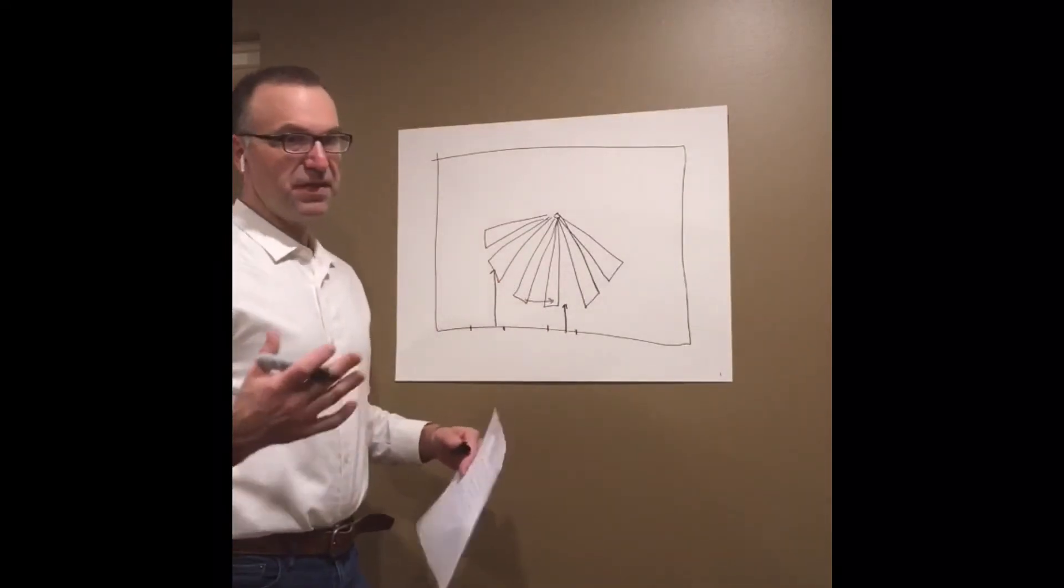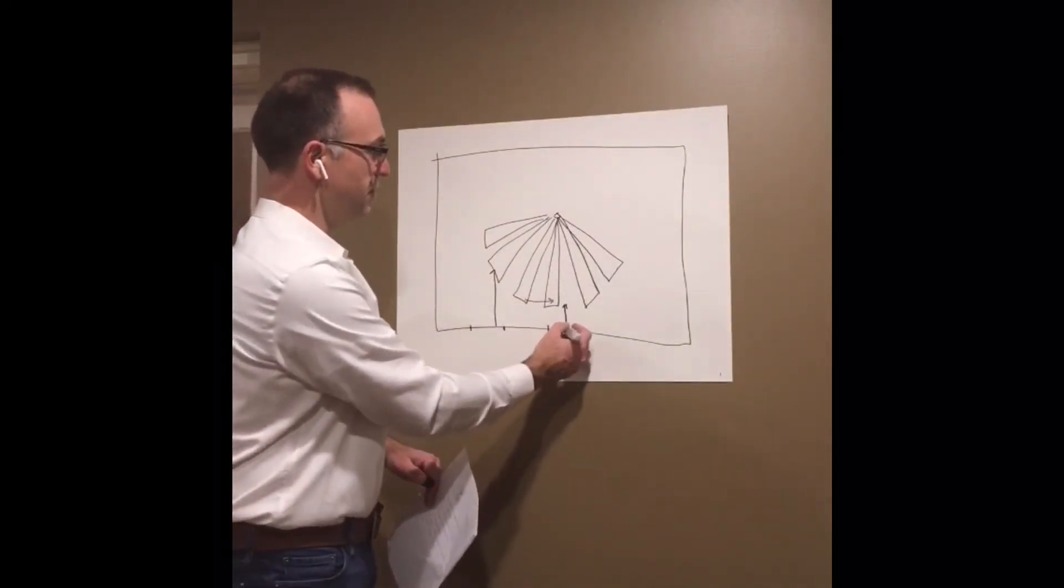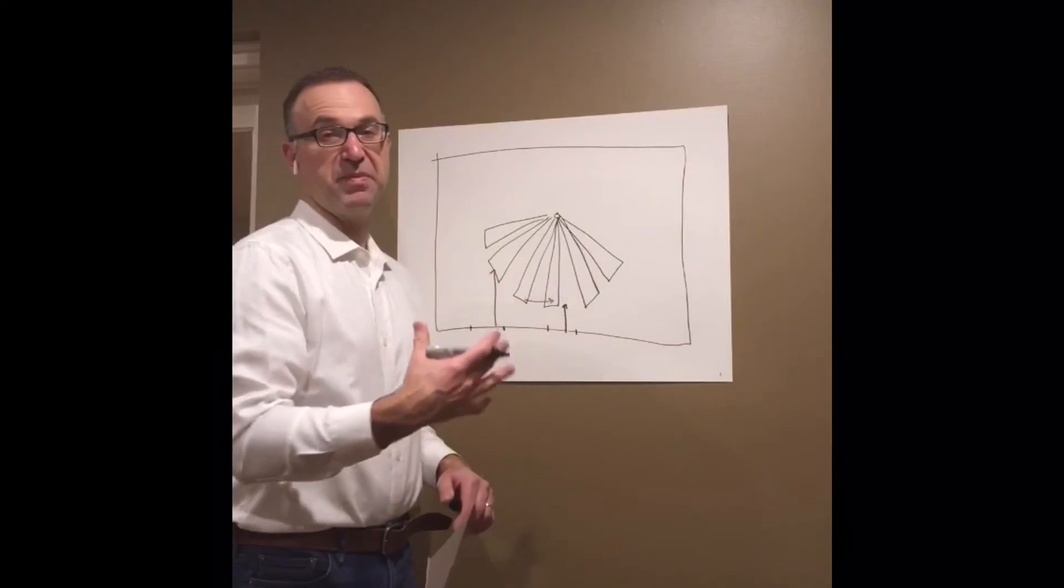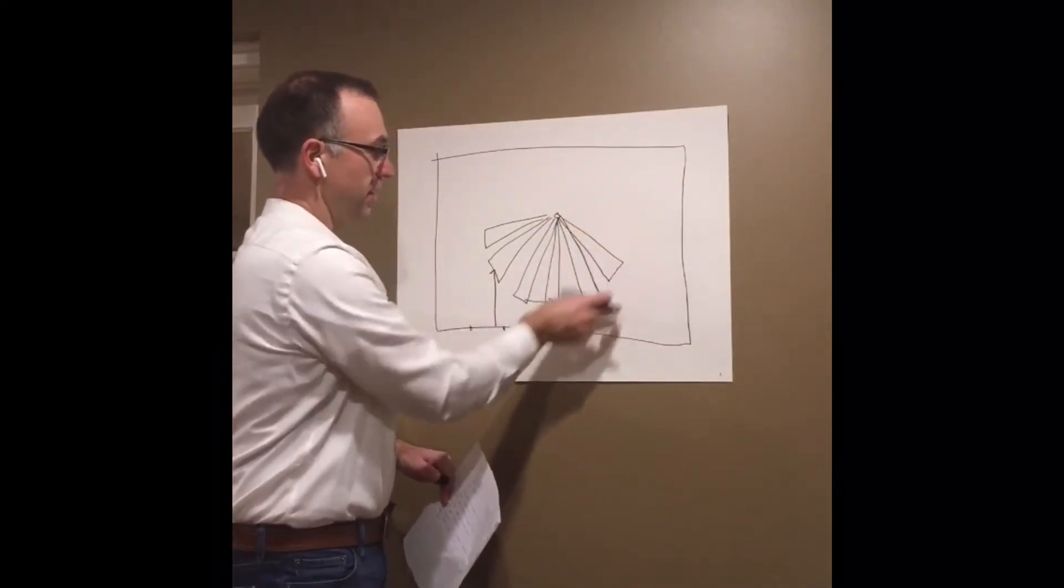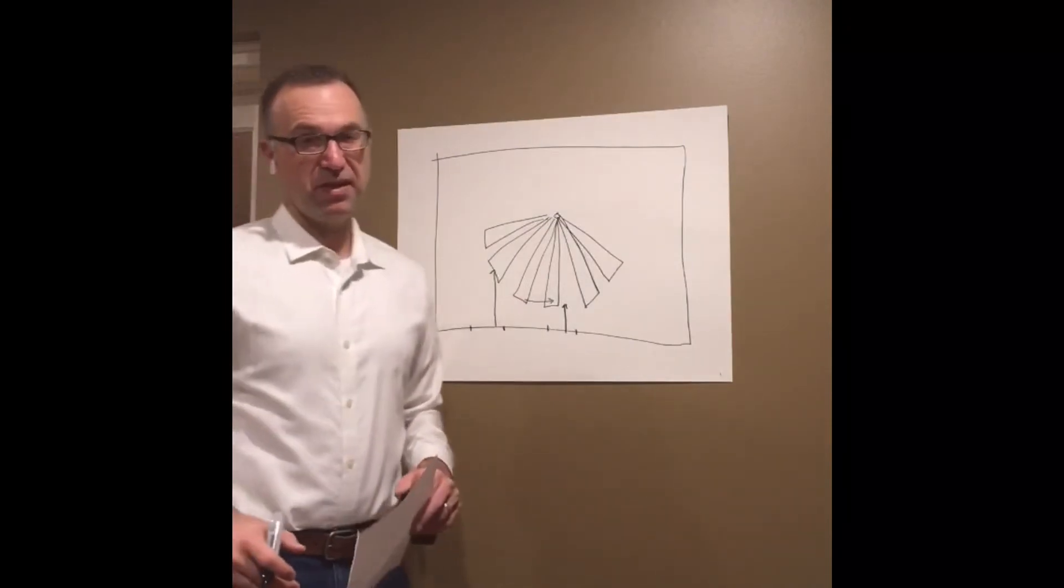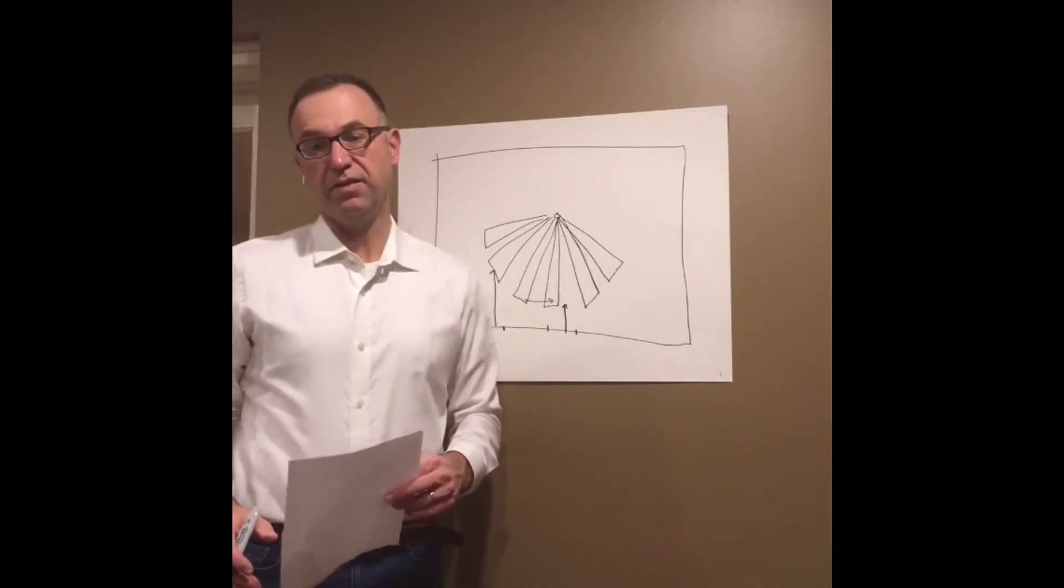So just something to think about with sensor placement. So if we had the door here and we wanted that sensor to pick you up immediately, we could slide it over just a little bit this way, and it would sense you better as you walk in the room.